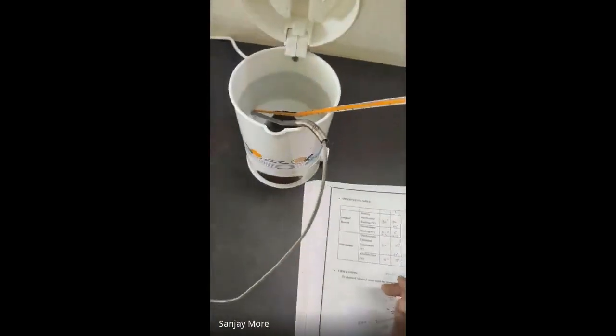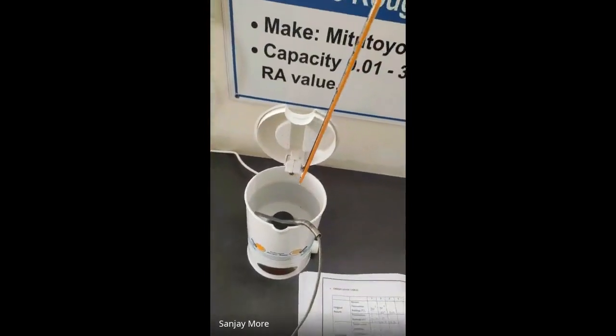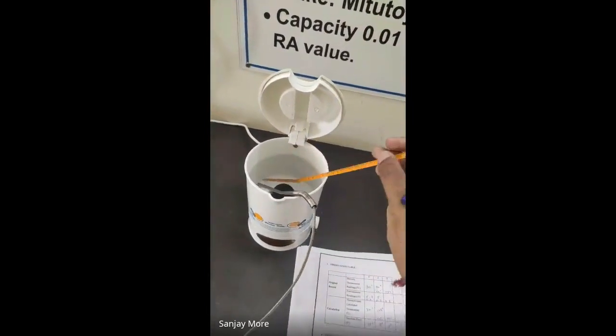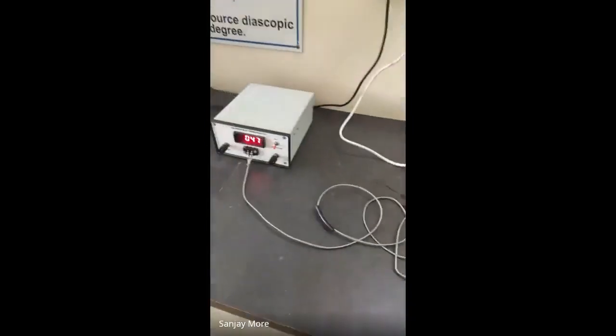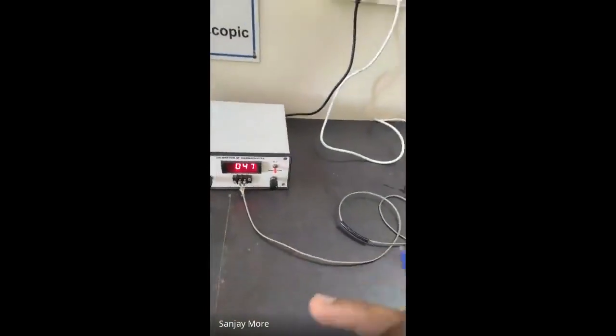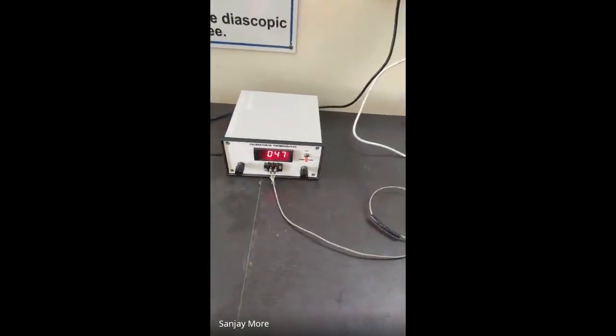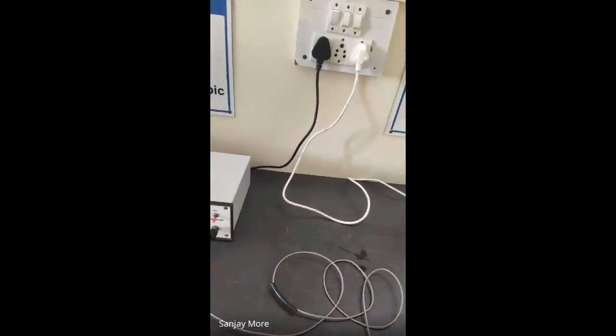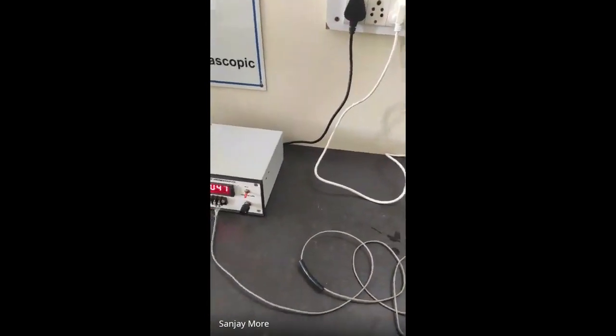Then you have to take repetitions of readings, 3, 4, 5 readings, and calculate the absolute error. This error shows the difference between the mercury thermometer and thermocouple readings. This thermocouple gives a 9 to 10 degree deflection or error in temperature measurement.